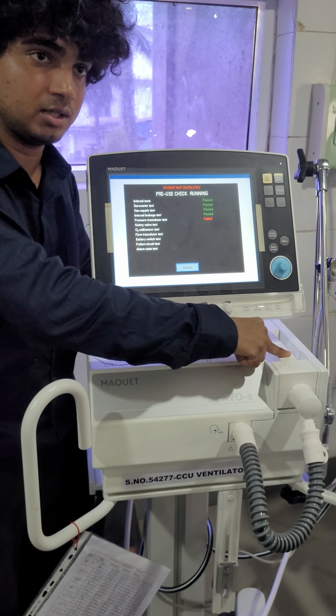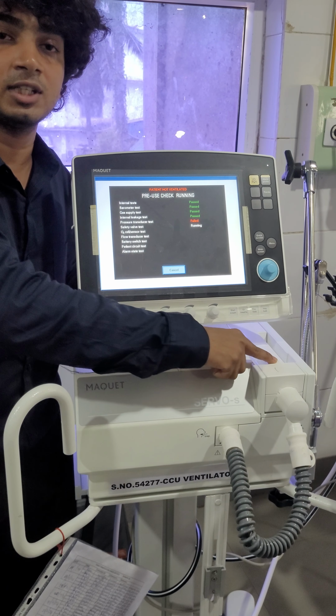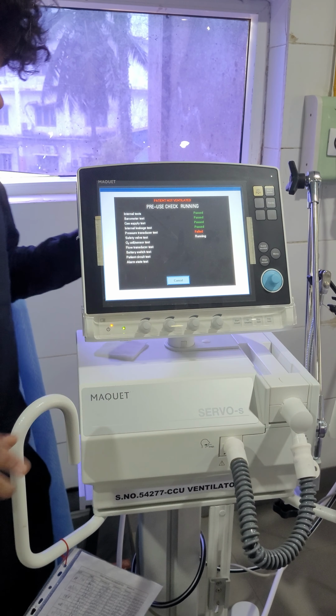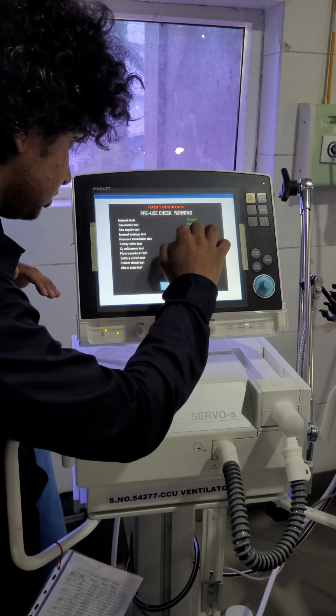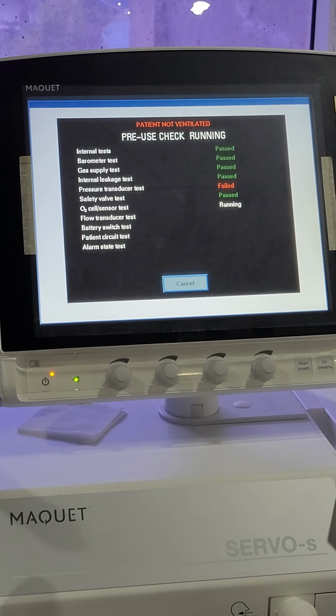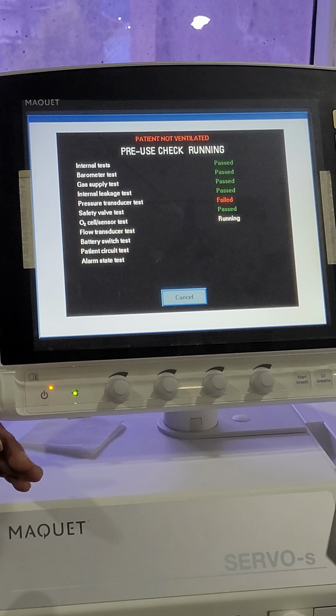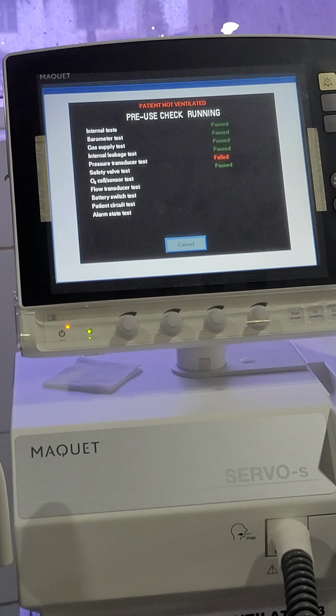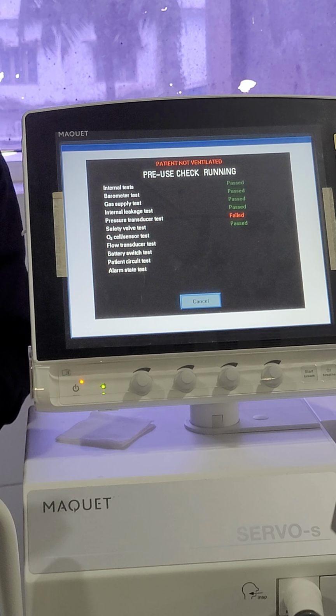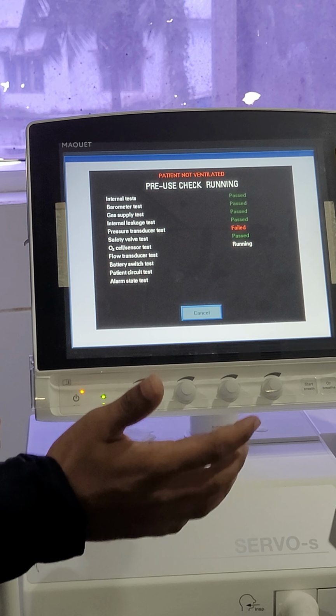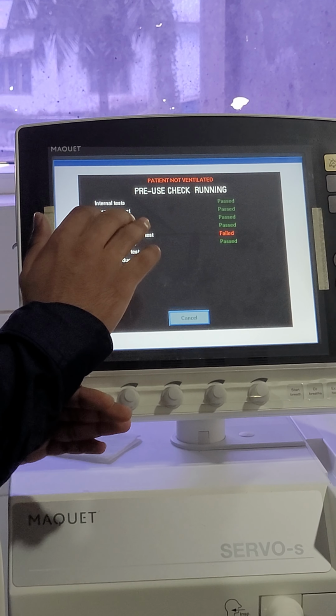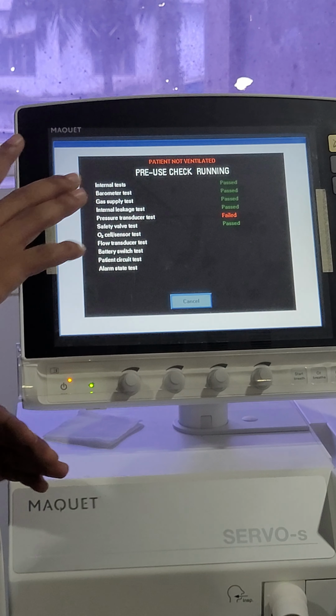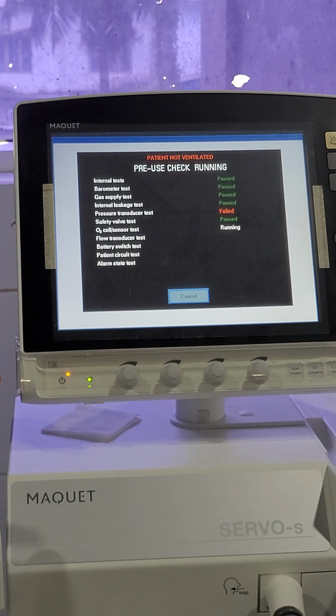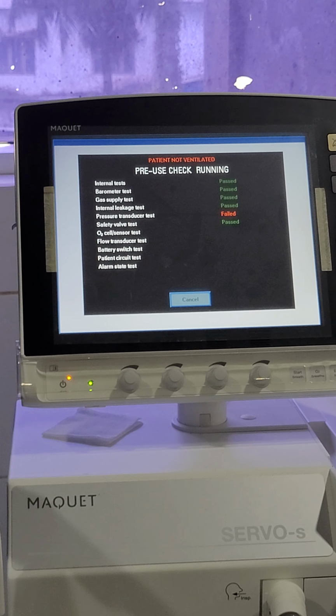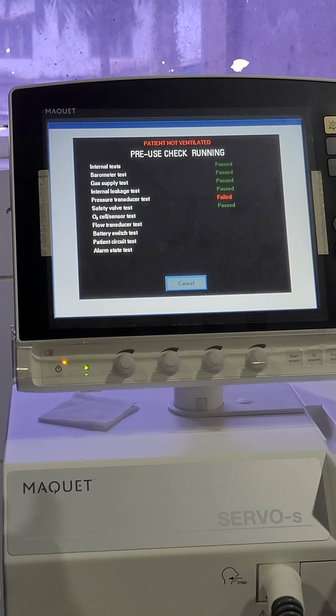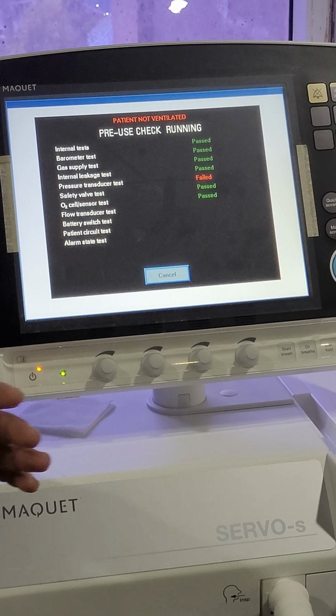This is the flow sensor. In the expiratory cassette, it is incorporated. So there is a pressure transducer failure. You have not done the calibration, so it will not give you the right value. The pressure going to or coming from the patient will not be measured correctly. This will be taken care of by the biomedical team. Usually, I'll teach later why that test is done. Can you hear me? It works on the ultrasonic principle.